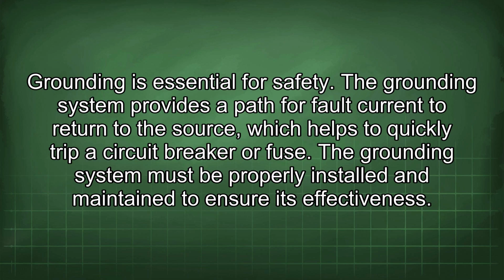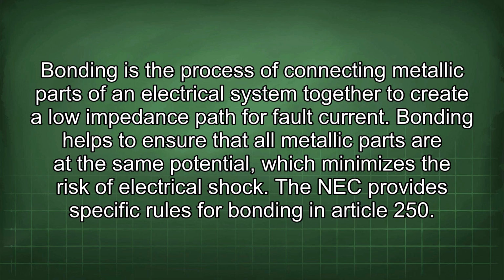Grounding is essential for safety. The grounding system provides a path for fault current to return to the source, which helps to quickly trip a circuit breaker or fuse. The grounding system must be properly installed and maintained to ensure its effectiveness. Bonding is the process of connecting metallic parts of an electrical system together to create a low impedance path for fault current. Bonding helps to ensure that all metallic parts are at the same potential, which minimizes the risk of electrical shock. The NEC provides specific rules for bonding in Article 250.